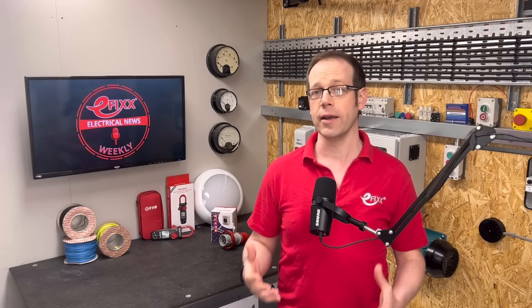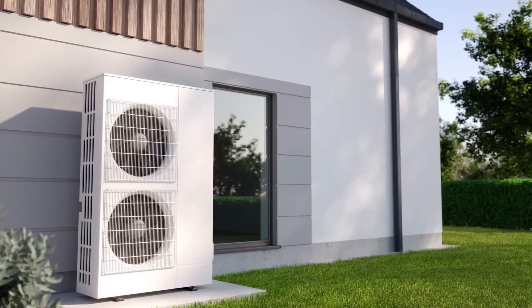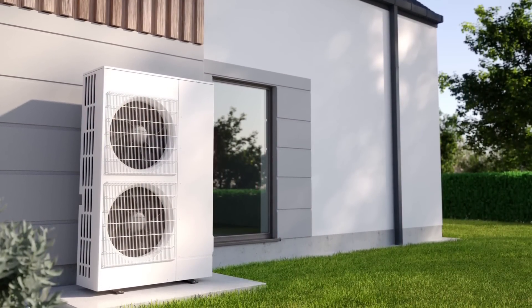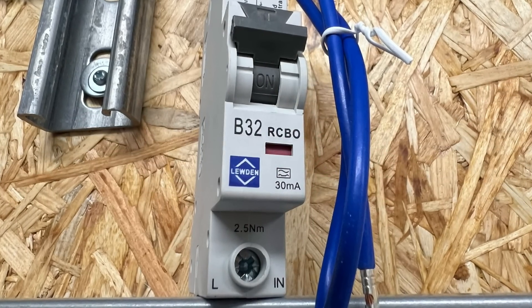A concerning number of installers are fitting the wrong type of RCD to heat pump installations. That's the revelation of an eFIXX investigation into the way the units are connected to UK homes. Heat pumps are equipped with inverter-driven motors that regulate the output. The power electronics that control the motor speed can produce substantial DC leakage current, potentially impairing the electronic circuitry inside the RCD used to protect circuits.